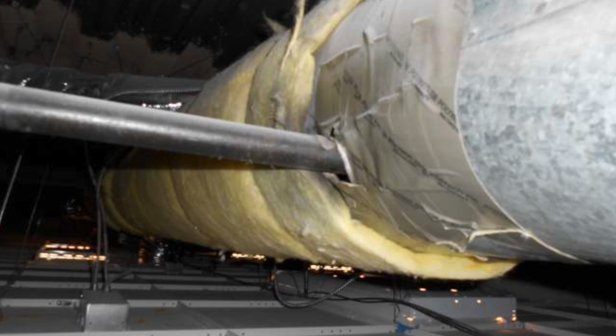It's not a liquid, but it is a fluid, and it acts the same way as any other fluids do. Path of least resistance. And if it was a liquid, we'd have stains all over our ceiling tiles because there's so many leaks above the ceiling. So when we walk into the facility and we see all these potentials, hundreds and hundreds of points of failure, gaskets at fire damper access doors, air handler accesses, penetrations where we've even seen fire sprinkler systems routed right through a main duct. And it's amazing that once the duct is installed, you can't keep track of what's happened above the ceiling after that ceiling tile is put back in place.